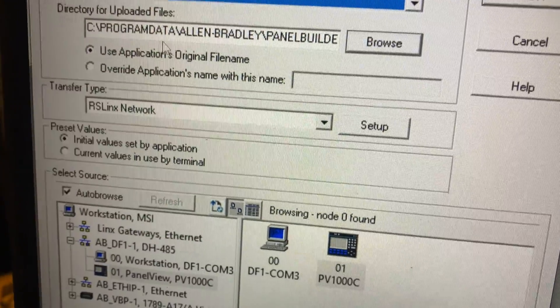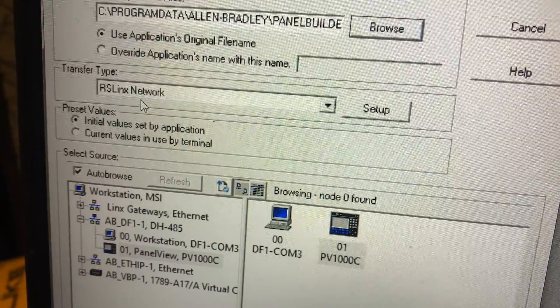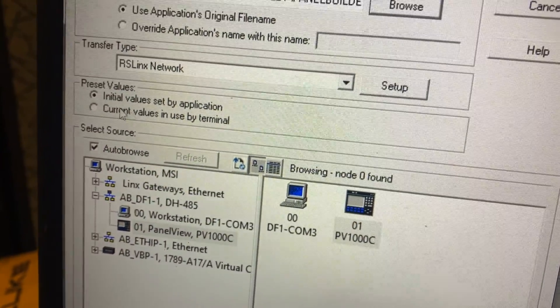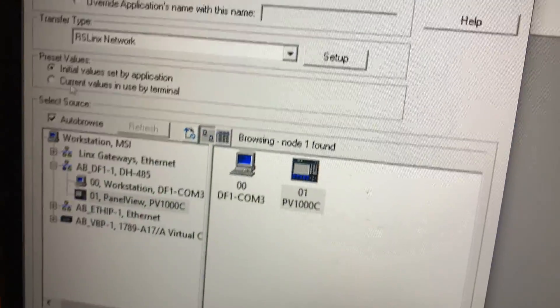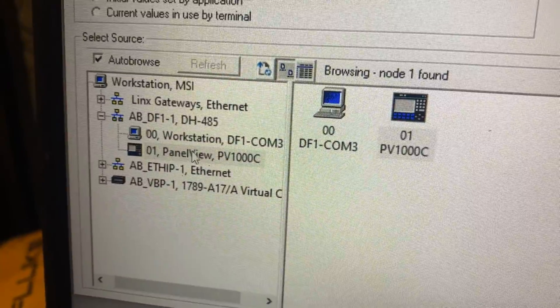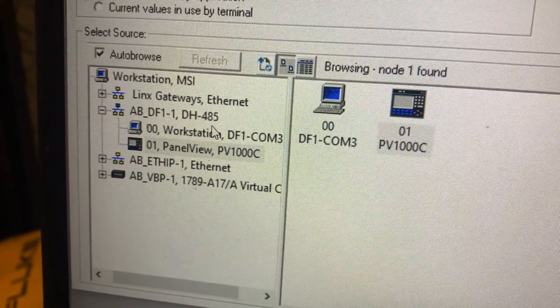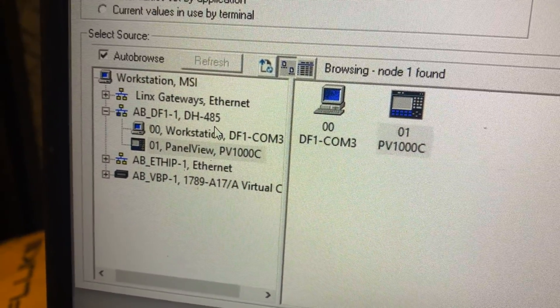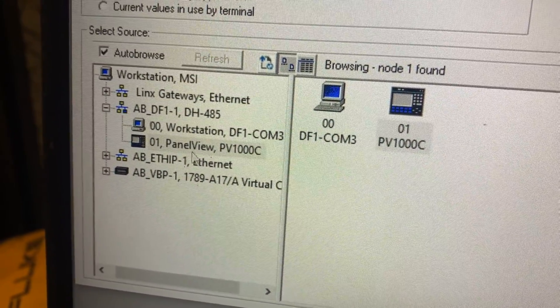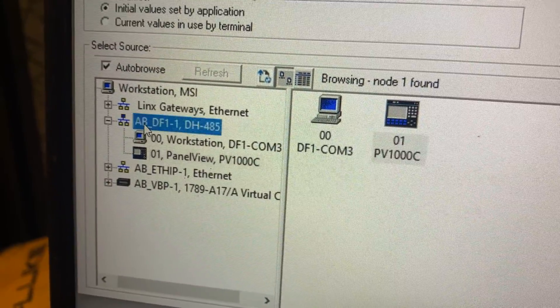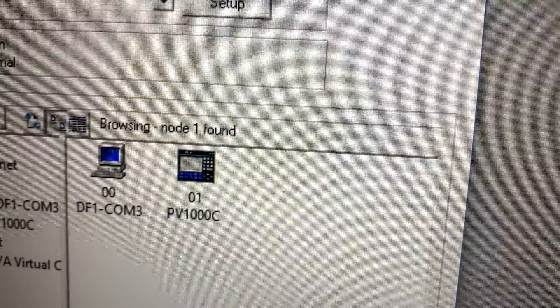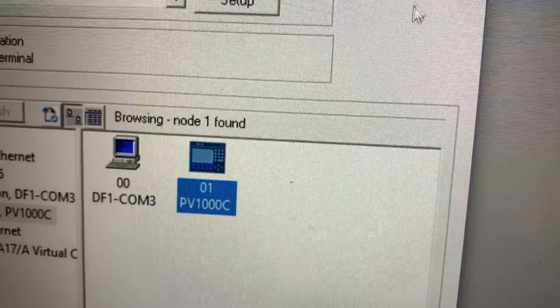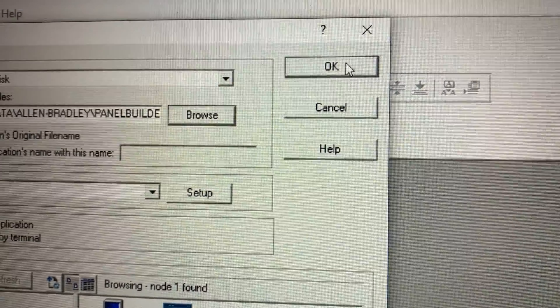Over here you can see at the top, Upload Application to Disk. It gives you an area to put it. Then we're going to do Transfer Type is RSLinx Network, and then all of the preset values, those are fine. You can see down here our AB_DF1_DH485 right there. We're going to click on that heading, the AB_DF1, and then in the right we're going to select our PV1000C and then hit OK.